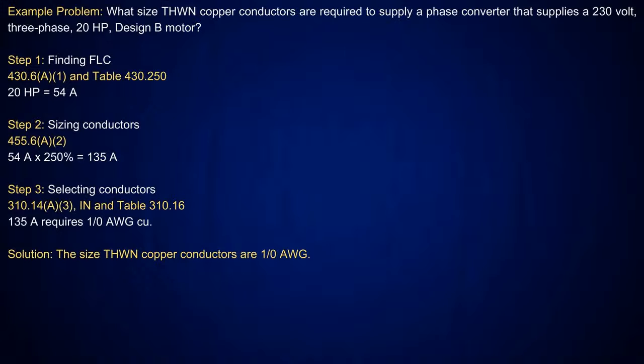In this case, we have a 3-phase 20 horsepower motor. It's good for 54 amps. But if you go look at 455.6(A)(2), it's going to tell you that it has to be taken at 250% for the conductors. Now, I'm not going to do it now, but when we get into the overcurrent protection devices, anybody that's watching this, I want you to remember what I'm talking about here, okay?